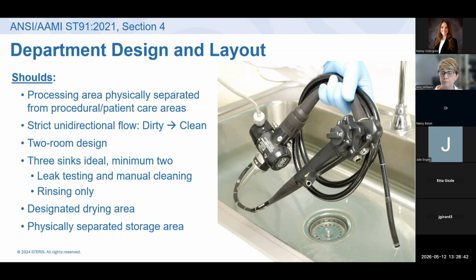We need more space. Ideally, there should be a 2-room design. You want 1 room for decon, separating that manual cleaning area from places where we're doing clean inspection, disinfection, and sterilization. So ideally 2 rooms, completely separate. If you don't have 2 rooms, you can use a 1-room design, but there should be a minimum of 4 feet between decon and the clean work area, so definitely a designation between those 2 spaces with a minimum of 4 feet. That 4 feet is always because of the droplet, the splash factor.